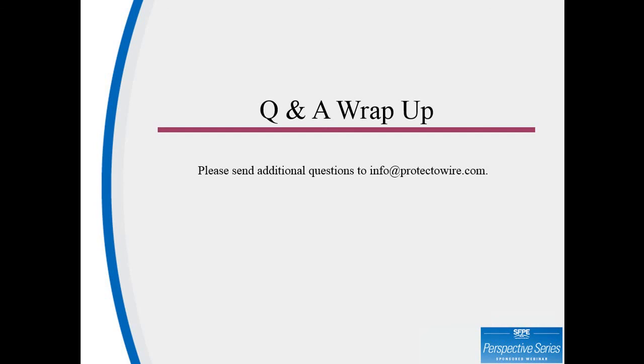What is the life expectancy of linear heat detectors? Technically, no specific service life for Protectowire linear heat detector exists, either by code or by recommendation. The service life is a function of the environmental conditions it's exposed to, for instance, chemicals, vibration or abrasion, support spacing and mounting accessories, and physical factors. As previously discussed, jackets are the protection for the detector and should be chosen correctly for the environment. Based on feedback from customers, our own use and testing, properly installed and serviced Protectowire will operate for decades.